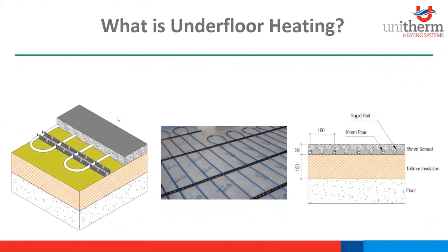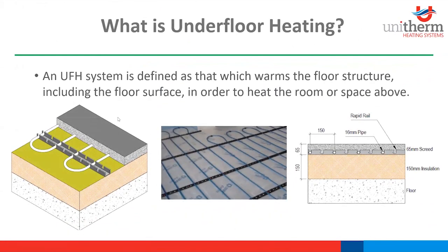So a bit on underfloor heating. Underfloor heating is defined as that which warms the floor structure, including the floor space, in order to heat the room above. Here you can see a cutout of a standard underfloor heating system, and these are the normal methods. The floor insulation is bedded on top of your concrete slab. Then you have a vapor barrier placed over this. Pipe tracking or a rapid rail system is clipped down to accommodate an array of pipes, usually at 150 to 200 mil centres. Then you have your sand and cement or liquid screed poured on top of this to create your floor structure and your thermal mass for heating.